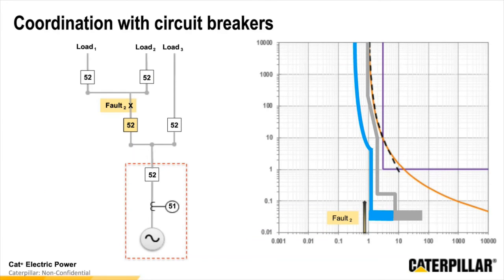And in the end, we will continue as we move more breakers into the system. We will continue to add more to the left of the curve. In this instance, we're looking at the system and saying, if we have a fault that occurred at location 2 here, and we still have that same discussion before, we would trip the breaker that's feeding both loads 1 and 2, but we would still be able to support load 3 within the system. So we're doing that selective coordination where the different protective zones are all being considered. We look all the way down into the loads, and we're making sure that we're protecting each level as we go down towards the system.